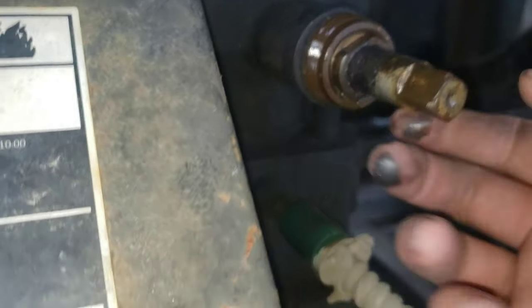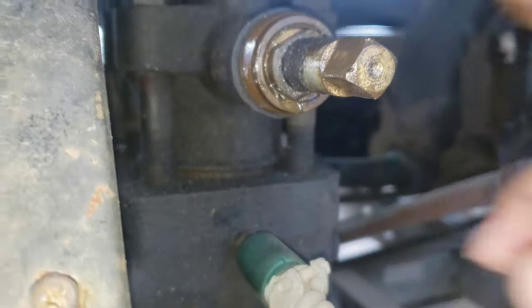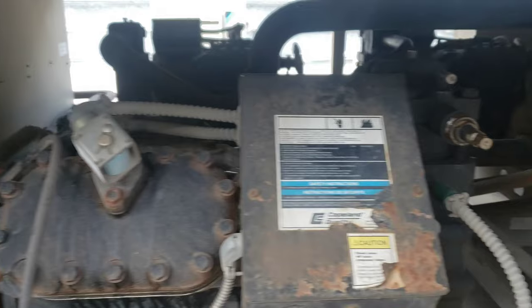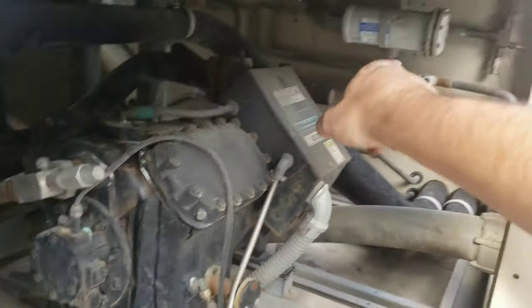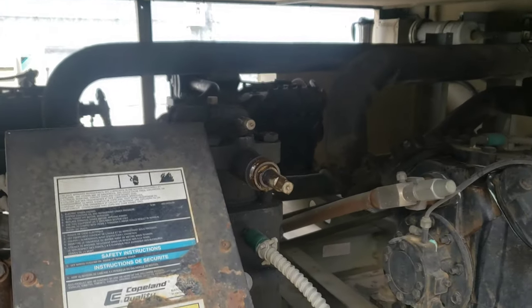The first step — and you can actually see it bubbling down here if you watch it long enough — those bubbles are from this leaking. We may be able to salvage it. All of these are leaking at the stem there, that one, that valve over there, so we're going to see what we can do to remedy that.